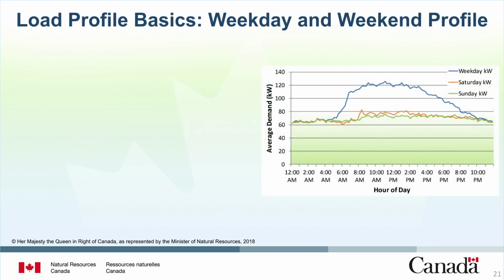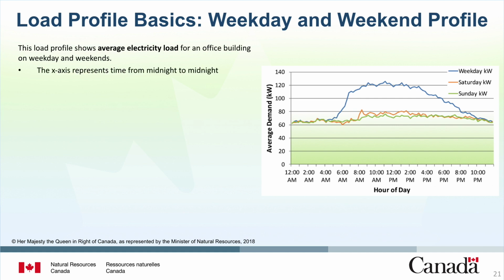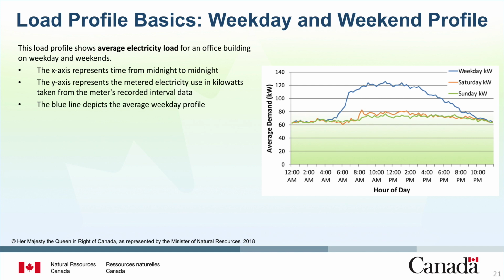Now let's compare weekday and weekend load profiles. The load profile on the slide shows the average electricity load for an office building on weekdays and weekends. The x-axis represents time from midnight to midnight, and the y-axis represents the metered electricity use in kilowatts taken from the meter's recorded interval data. The blue line depicts the average weekday profile. The orange line shows average load on Saturday. The green line represents the average load on Sunday.